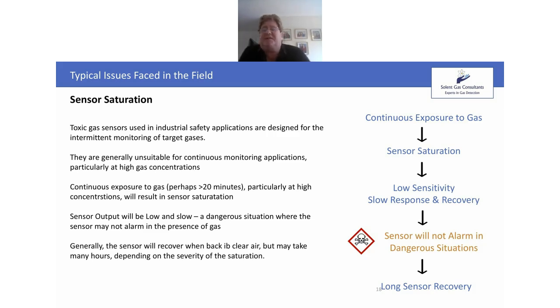Sensor saturation. So this commonly happens. The sensor is designed to measure up to a certain concentration. If the sensor is exposed to too high a concentration for a length of time, then it would become saturated, and you would then find that the output would become low, and its response and recovery would be very slow. Usually, when the sensor is put back into clean air, it will recover, but it could often take many hours to do so. So exposure of these sensors to very high concentrations over lengthy times should really be avoided.